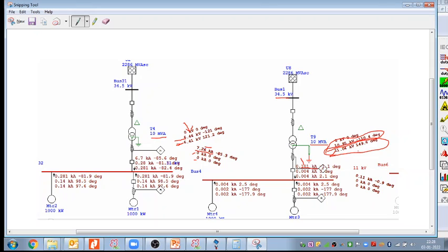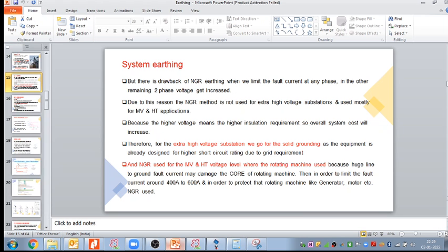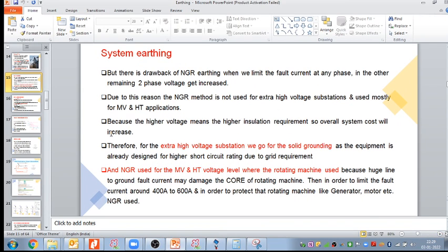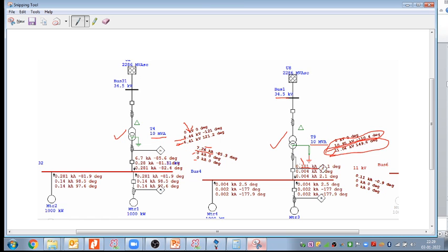So where we use NGR, where we should go with the solid grounding, the difference is clear, right? Now, where we go with the solid grounding, where we should go with the NGR grounding. What is the selection? Due to this reason, the NGR method is not used. The drawback of NGR earthing: if my slide is not clear, I will zoom here. When we limit the fault current at any phase, in the other remaining two phases, voltage gets increased. As we can see here, voltage gets increased, right?